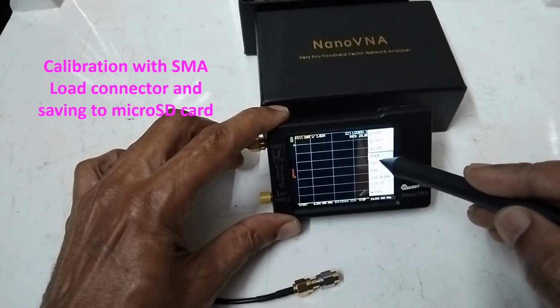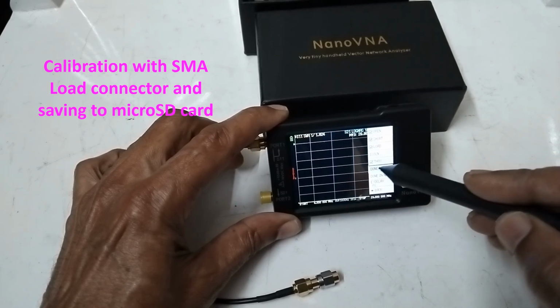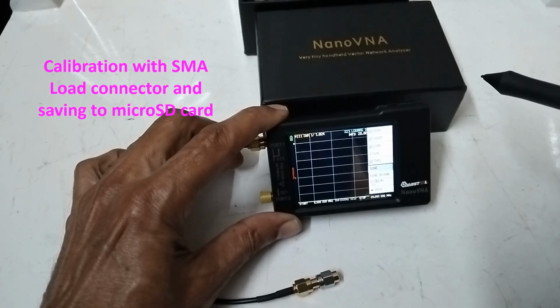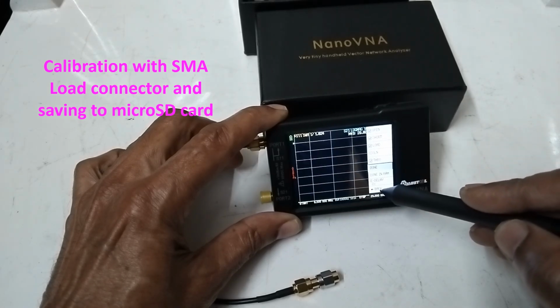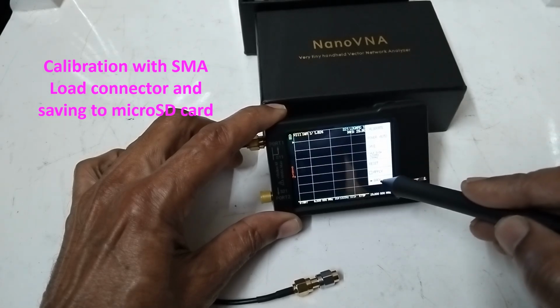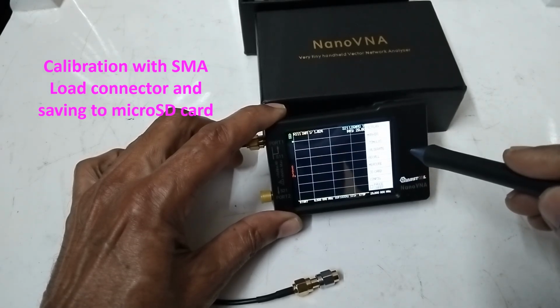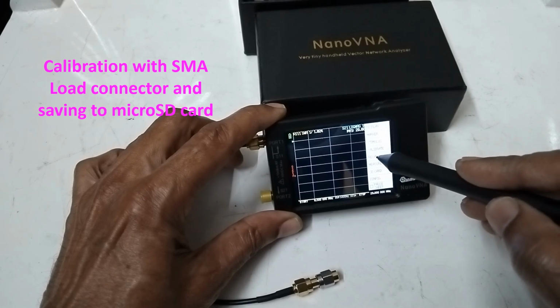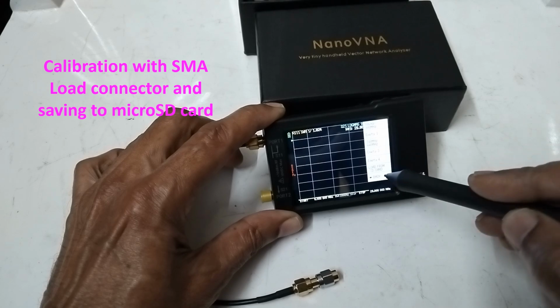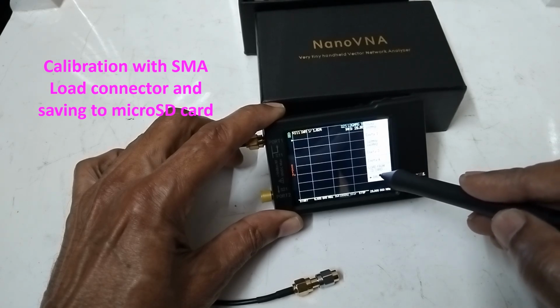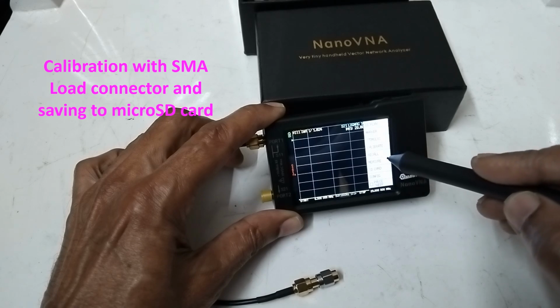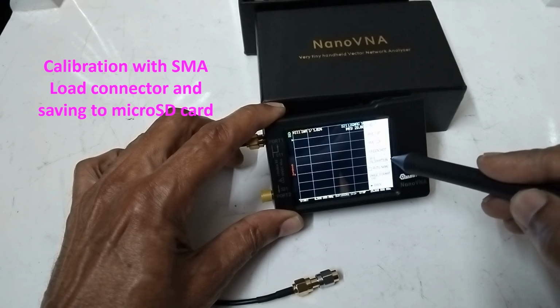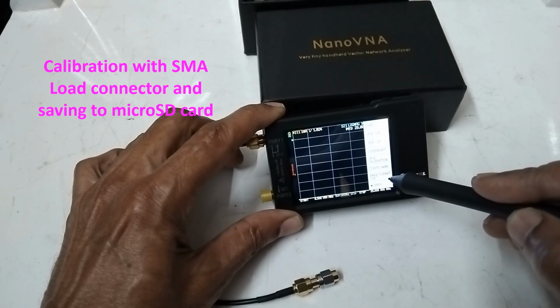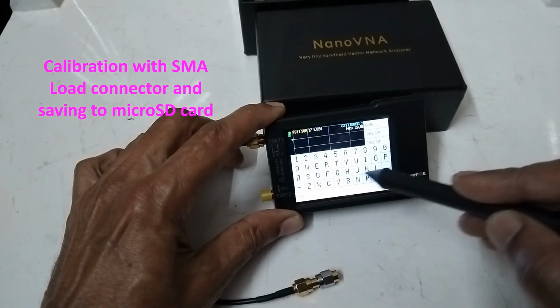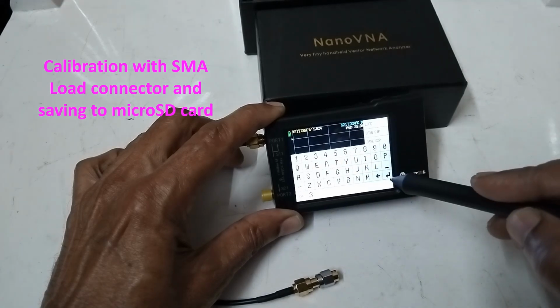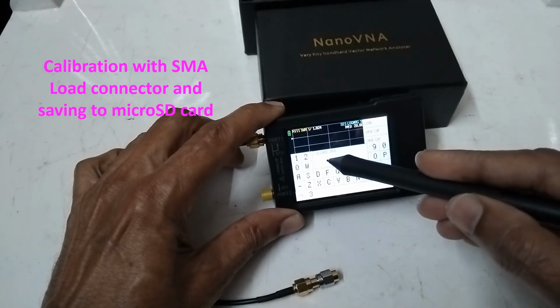SMA load also has been calibrated. Now I'll just move through isolation and done because I'm not using all those for this SWR measurement. Back. I'll just recall and see. Actually I have not saved it. I'll better save it to the SD card. Save calibration. I give another channel, 3. The other channels I have used earlier. So save to calibration 3.